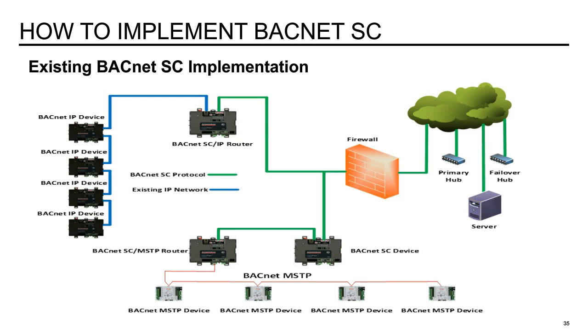Okay, next question from Akila. With BACnet SC being approved, is BACnet IP going to be phased out or discontinued? I think the short answer is that we will see an industry movement from BACnet IP to BACnet SC devices, because they will provide the security that's required by IT departments and that owners and facility managers are going to want in their buildings. How long it takes to happen, I'm not sure. I would say it's going to be a few years, just because of the number of BACnet IP installations that are out there right now.